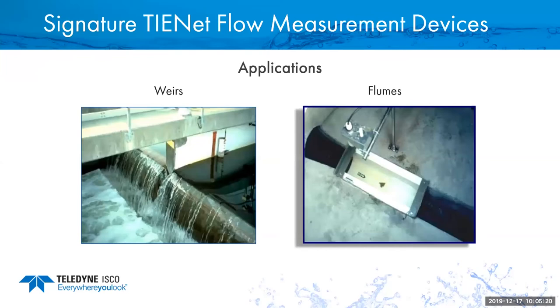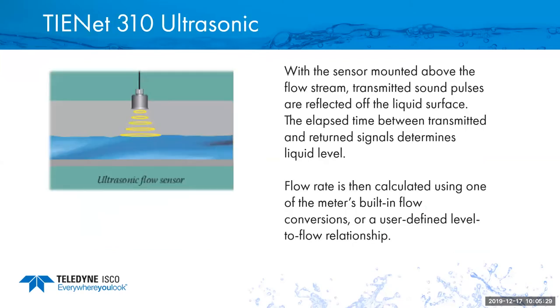Now, looking at the different applications where you could put some of these sensors, there are weirs or flumes, meaning you need primary devices to measure the flow through the channels. With the 310 ultrasonic, the sensor is mounted above the flow, non-contact, using sound pulses, ultrasonic signals, to measure the distance to the surface of the water and therefore calculating the level of the water in the flow. Then by knowing what kind of primary device you have, the level calculates into a flow rate. So it's great for that kind of situation where you already have a weir or flume, or are installing a weir or flume, and you want to install something that's non-contact, not in the flow.